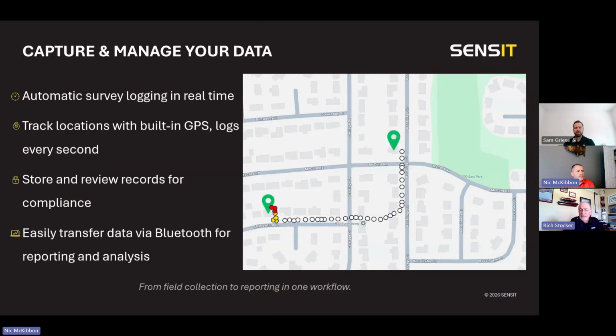And then, of course, the data. Nick, do you want to take over and talk about the data capture and the calibration? Sure, absolutely, Rich. Thanks. We are providing a tool that has built-in GPS and data logging capabilities, like Rich said. With that data logging capability, it's automatically capturing those readings on your work display, and we can set that interval. It's capturing that data at every second. So every second the data logging capability of the unit is automatically capturing that for you, so you don't have to sit there and manually press the C button to save that data.